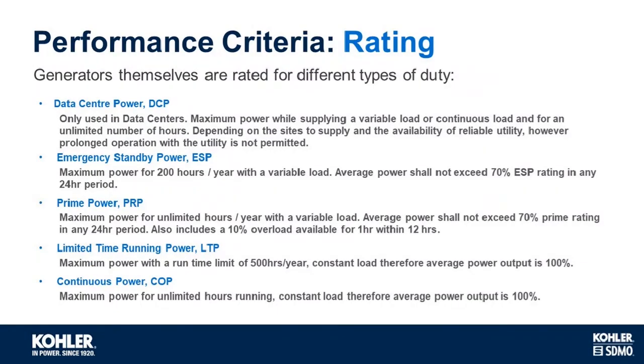ISO 8528 also sets out the different types of generator ratings, starting with data centre power, so only used in data centres, and the maximum power while supplying a variable load or a continuous load for an unlimited number of hours. However, prolonged operation with the utility is not permitted. Emergency standby power, so that's the maximum power for 200 hours a year with a variable load, and the average power should not exceed 70% of the rating in any 24-hour period.